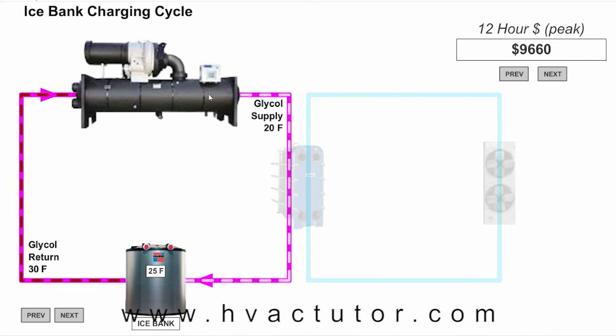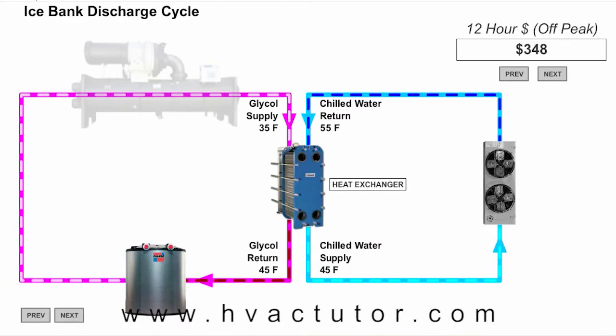We are circulating glycol from our chiller through our ice bank in order to freeze the water. During the peak hours, we turn off the chiller and we circulate the glycol through a heat exchanger, and our chilled water is being cooled by the glycol instead of being cooled by the chiller. As the glycol is being circulated through the ice bank, it is raising the temperature of the ice, and eventually when it reaches 32 degrees, it will melt the ice. Depending upon the volume of ice that we have produced, we can run this for a very, very long time.